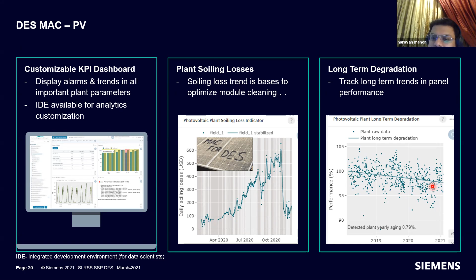For PV, the asset monitoring package we provide includes availability and yield at 15-minute intervals. If needed, we can reduce the interval to 5 minutes, or even reduce it to 1 minute, though people don't usually ask for that level of detail. We report yield every 15 minutes: the energy performance index, availability, how much energy is generated, and performance ratio, which is a critical parameter for solar.